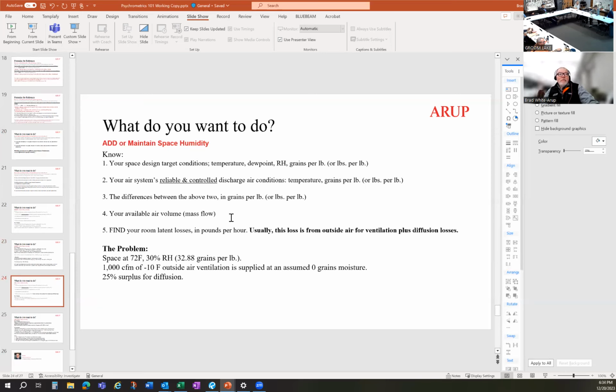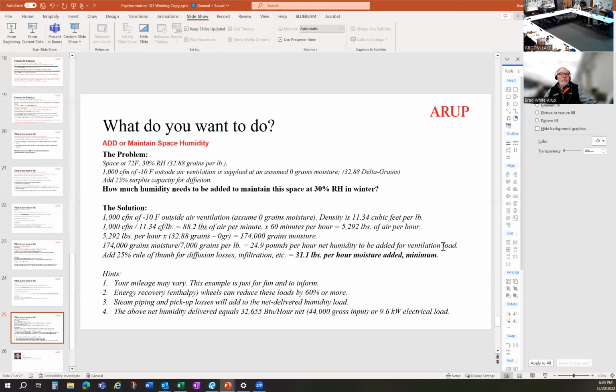Now, if you want to add humidity, again, it goes down to delta grains. I've got a space at 72 and 30% RH. I want to keep it at 30% RH. I'm bringing in 1,000 CFM of cold outside air. And I'm going to assume 0 grains moisture because that's a pretty fair assumption. And I always throw in 25% surplus for diffusion just because you're not just taking outside air, but you also have infiltration and other forces of vapor pressure pushing the moisture out into the colder, drier outside air. And I break down the problem, the solution, the calculations. Pretty straightforward. It's pretty much straight math.